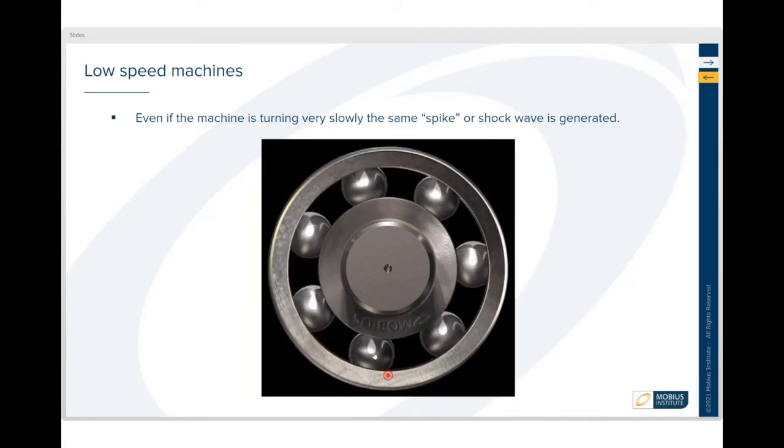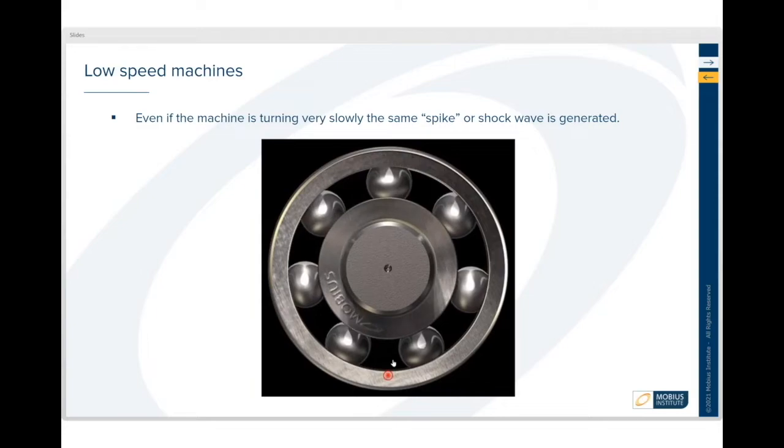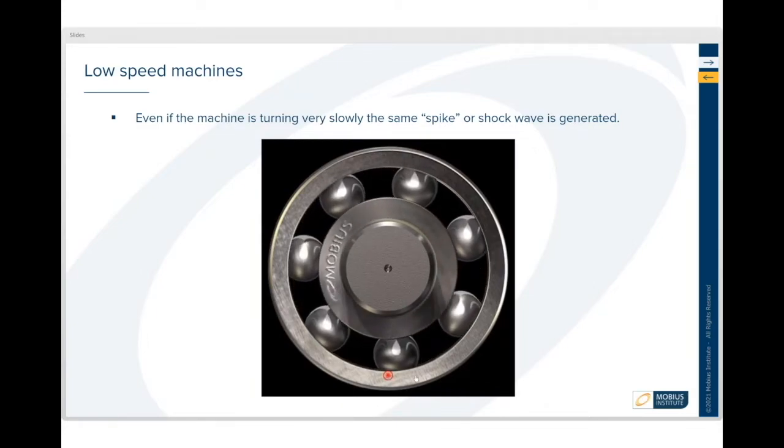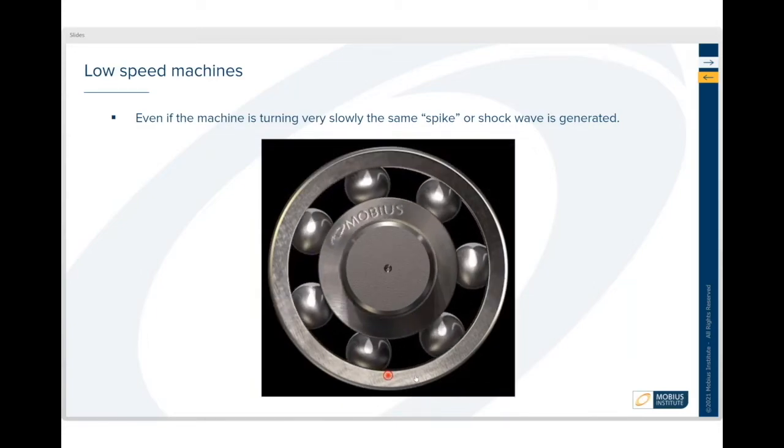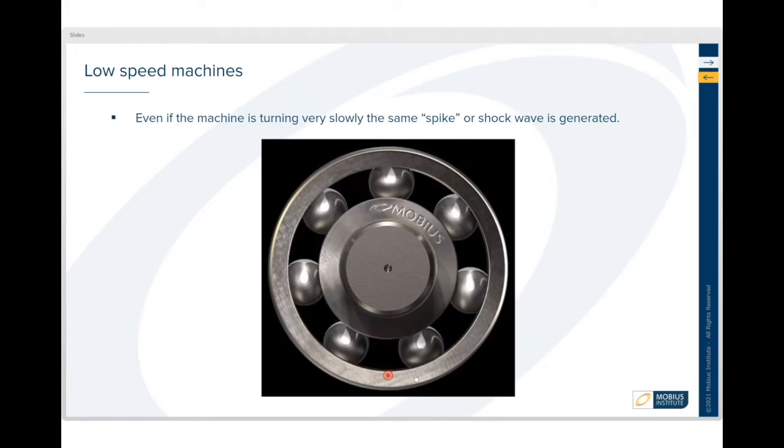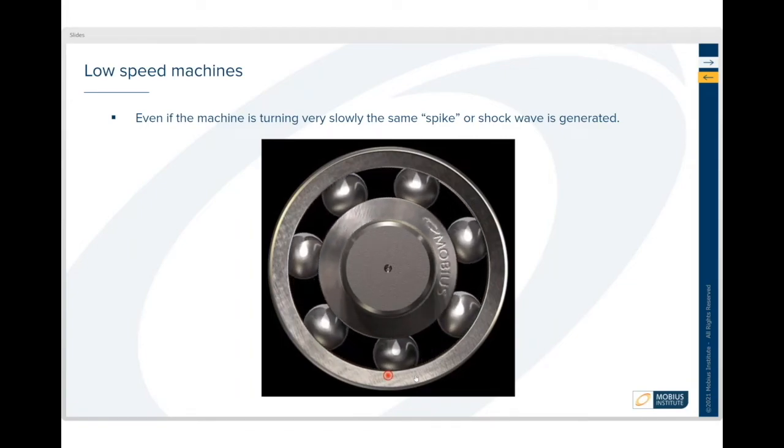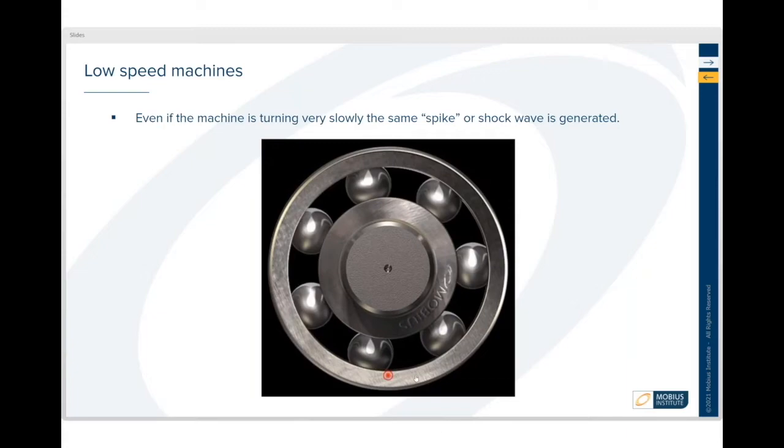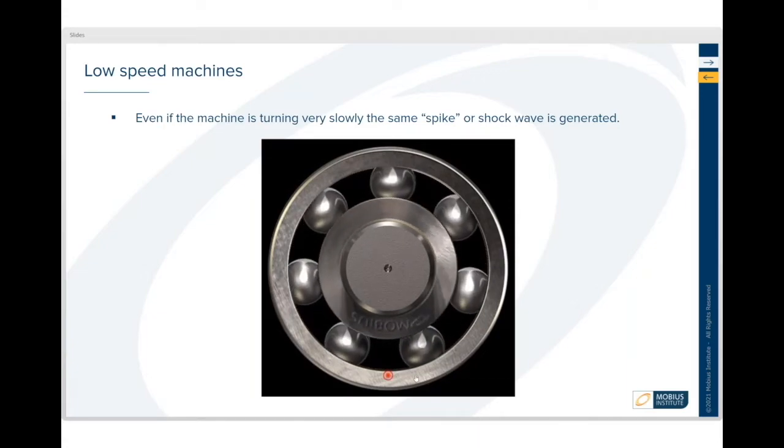The fact is that every time the rolling element rolls over the damaged area on the rolling element, on the inner race or on the outer race, there will be that same spike or shock or the ultrasound generated. And if we measure correctly then we can detect that at an early stage.